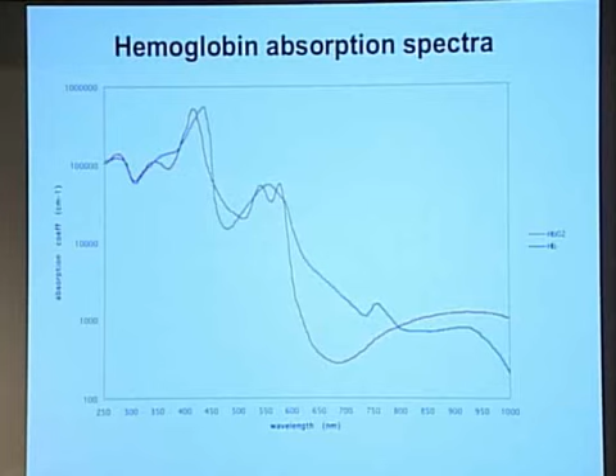The red light that I was showing here before got through fairly easily. This gets through fairly easily. And it takes advantage of this thing called an isosbestic point, where the absorption coefficients of oxy and deoxyhemoglobin are the same. So it's like a nice pivot point, a measuring point. It means that at this wavelength, at 800 nanometers, the absorption coefficient is independent of the stoichiometry of the hemoglobin. So they can tell whether the patient's oxygenation is going up or going down. These devices don't work very well to give you an absolute value, but once you calibrate it for that patient, they do a pretty good job of telling you whether it's going up or down.